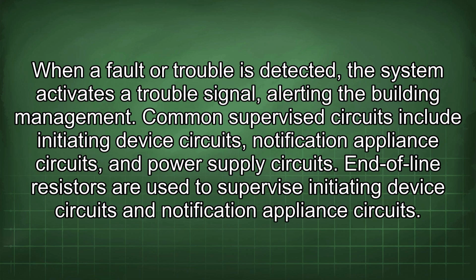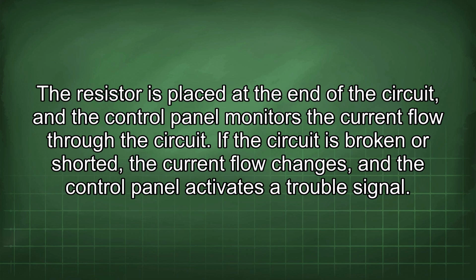Common supervised circuits include initiating device circuits, notification appliance circuits, and power supply circuits. End-of-line resistors are used to supervise initiating device circuits and notification appliance circuits. A resistor is placed at the end of the circuit, and the control panel monitors the current flow through the circuit. If the circuit is broken or shorted, the current flow changes and the control panel activates a trouble signal.